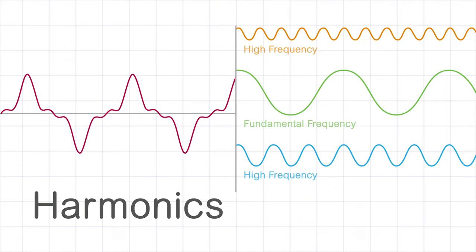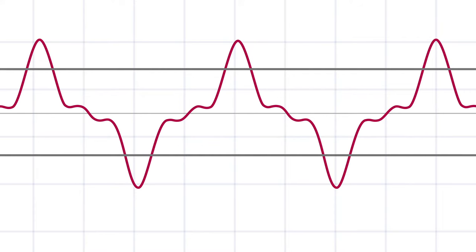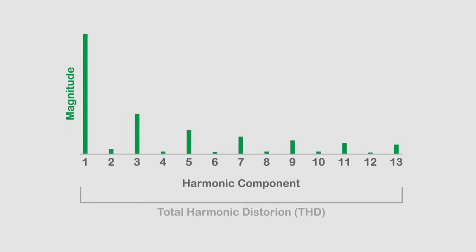Harmonics are high frequency current and voltage. These stress the electrical distribution network being that most electrical distribution networks are a stiff or low impedance system. Voltage distortion can cause distortion of control signals and stress electrical equipment's dielectric material.